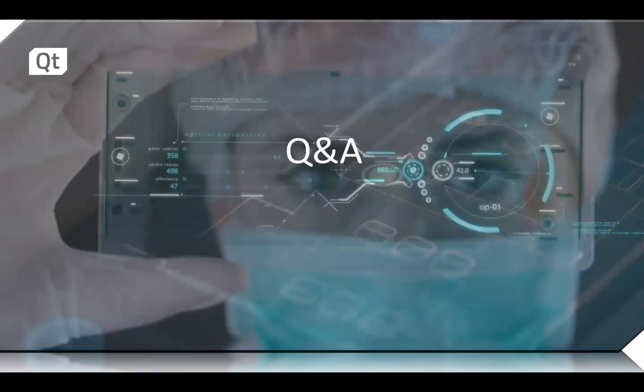That's a great question, and we get that question all the time. In speaking with our notified body, the safety classes in 62304 are A, B, and C. However, Qt itself is not a medical device. So the risk analysis is done on our customer's side to classify their device into safety class A, B, or C. The concern here is, is Qt in safety class C, the highest risk safety class, and developed into that?